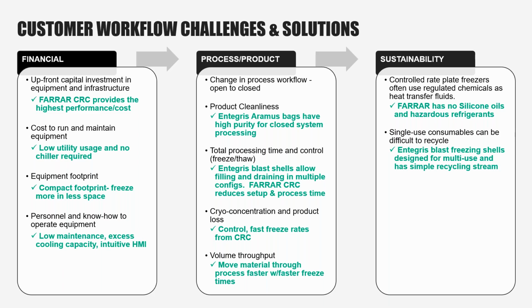The cost to run have been addressed, of course, by the Model 4000 because limited units are needed to run the process because of its speed. And the ability to use an air-cooled system means you won't have to install a chilled water line to cool the compressors. Finally, the excess cooling capacity, remember that 1616 watts of available capacity provides plenty of cooling power without stressing the compressors, leading to low maintenance and high reliability. The easy-to-use HMI also makes standing up lines fast and replicating them in other locations very easy.